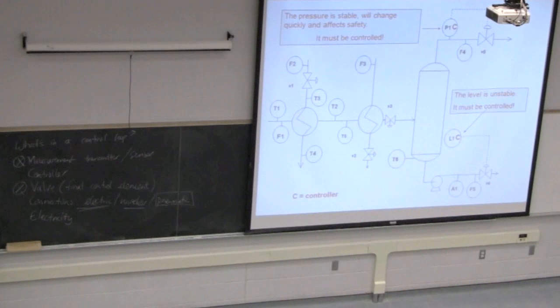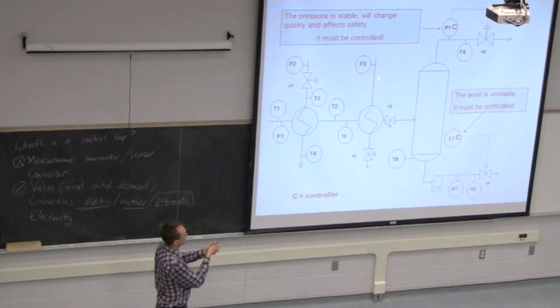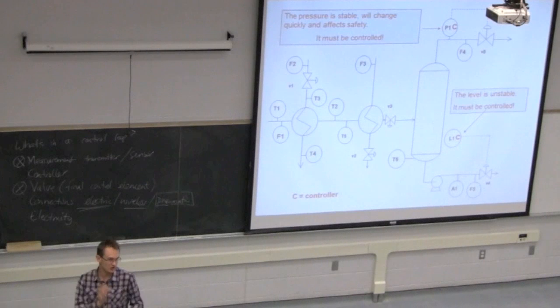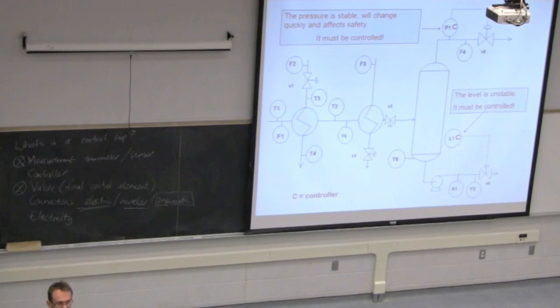Yes. For me too, because the valve is on the right side of the heat exchanger, we should not be worried about building up pressure inside the heat exchanger. Or just reach a dead end. The fact that it's on this side or that side doesn't matter too much because you're stopping the flow. So it's just flow that's not going anywhere.